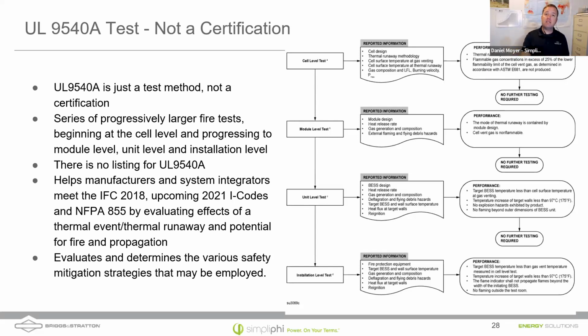They repeat that test at the module level and then at the unit level. And at the unit level, we were able to show that we didn't have any deflagration, which is a fancy word for explosion, no flaming occurred.